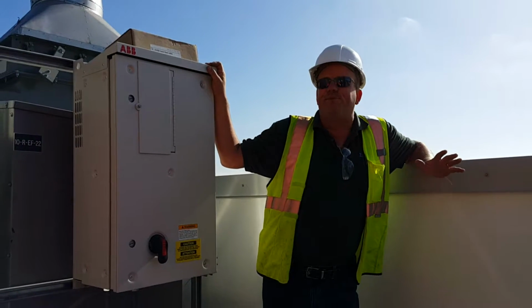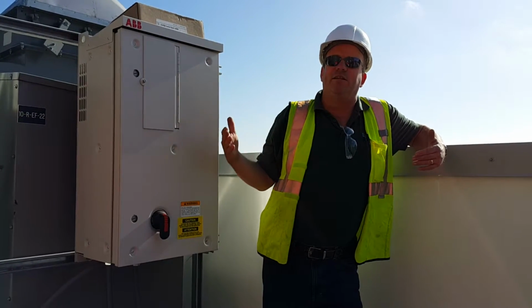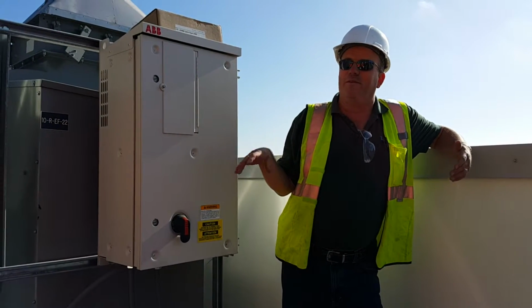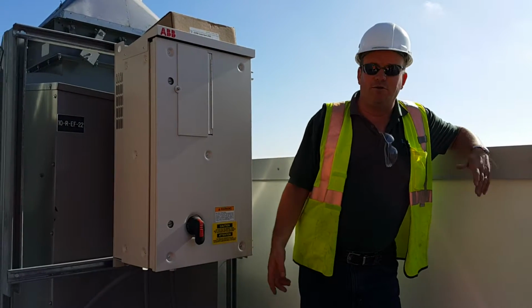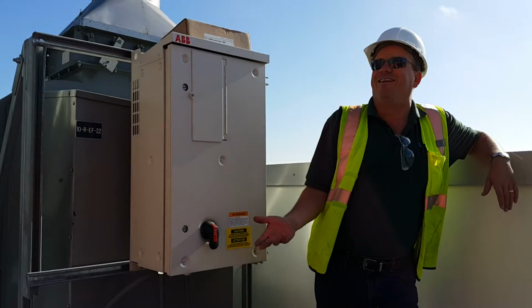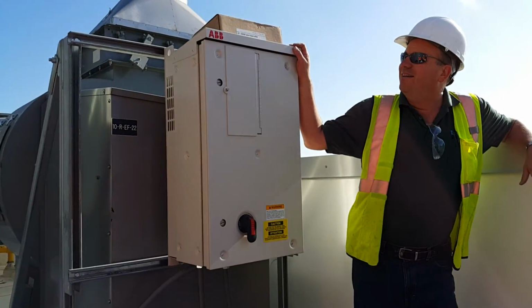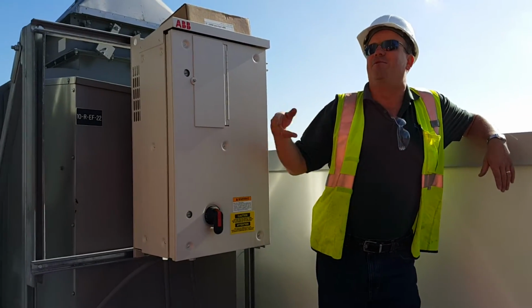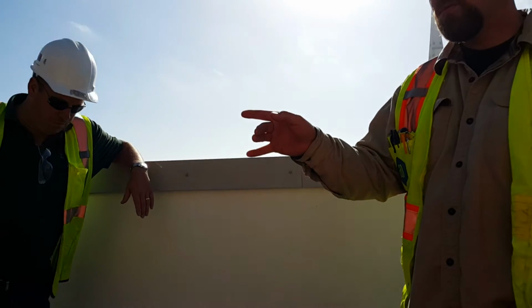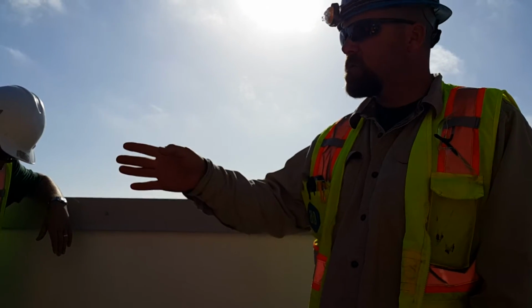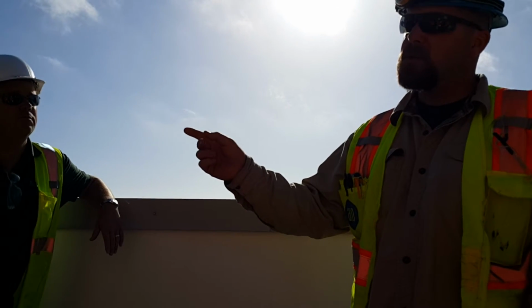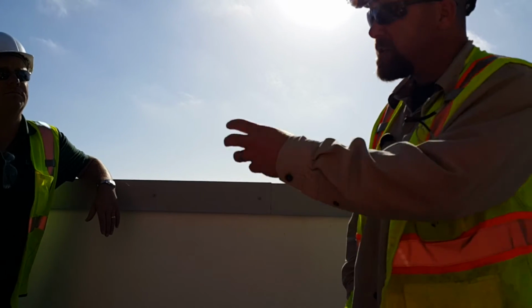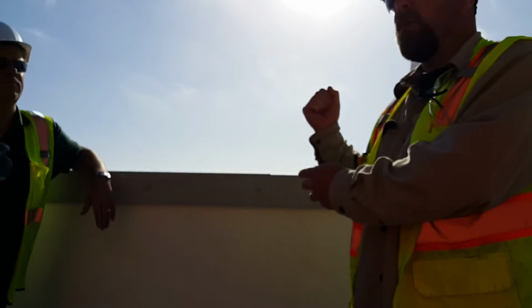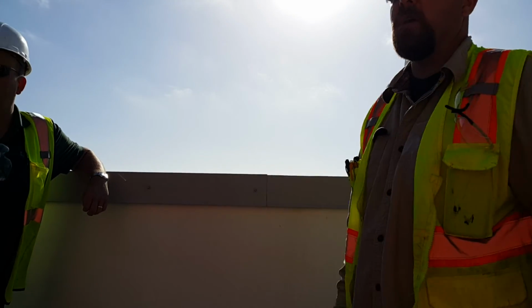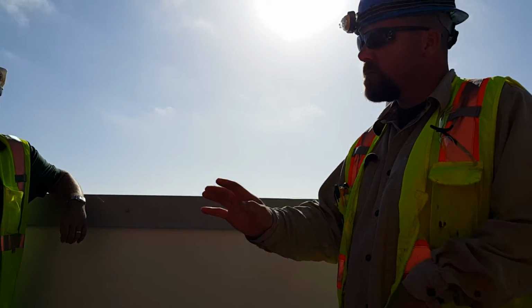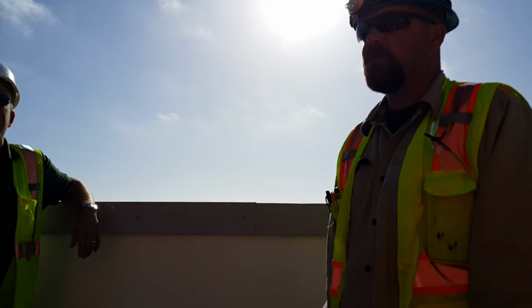Okay. Because sometimes it happens, the fire shuts it down, and the logic in the BMS system, some of these guys, I don't like the way they do it, they go, oh, I'm telling you to start, and you're not starting, so don't start. They'll take away the start command. Well, if it's not starting, who cares if you have the start command or not, right? So then sometimes at the BMS system, you got to clear it. We got 2 air handlers in our current building that we have to manually restart after an alarm. Yeah. So the way these ones are wired, fire alarm is interrupting at 24 volts going to the interlocks on the drive. So BMS is still sending their signal. We're just taking that voltage away for fire alarm, and then we put it back when things clear, and it picks it back up where it left off. Okay, great. So when you're in a fire mode, BMS thinks everything's just fine and dandy. We just switch the voltage. Okay.